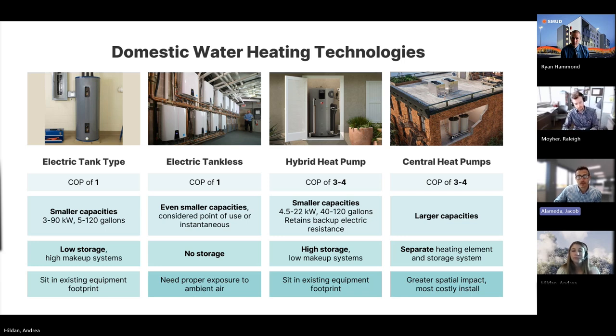However, similar to what we talked about before, you have to make sure that you have a significant enough amount of a heat source in that room to avoid freezing out your space and forcing that unit to trip over to electric resistance and running on electric resistance heating all of the time. So if there's not enough heat being naturally generated in the room that you use as your source, you kind of have to get creative with that. For example, I've seen some people dump the cold air, actually duct it back into the return plenum and things like that to make it work. But then the last option on the right is for buildings with more significant domestic hot water demand. This is a very similar concept to the last one, but you have an outdoor unit now grabbing that heat from the outside air, so you don't have to worry about overcooling a space.